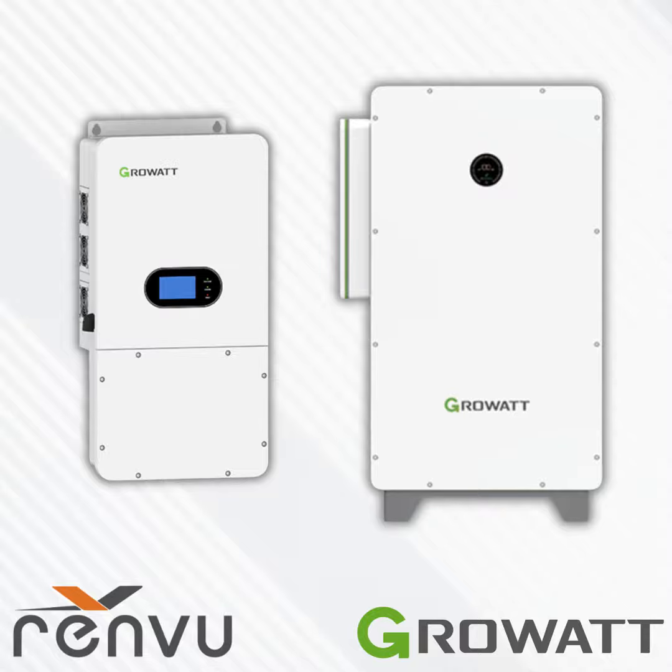Here's another example of a completely, I'm going to say it's an on-grid system with battery backup. So everything looks the same as before, except now we have an extra primary load that's connected to the load port of the WIT. In the event of a grid loss, our unit will automatically disconnect from the grid and keep load on the load port only. So there's no power on the grid port. If you want it to turn off with the grid, you can just connect it to the grid port. That's what we call our secondary load. If you want it to remain powered on throughout the life of the batteries, then you can put it on the load port and it will keep the unit powered on.